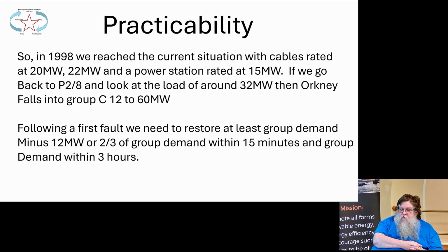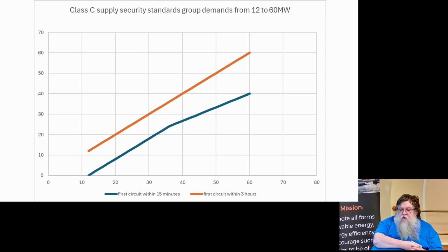If we go back to P2/8 and look at the load of around 32 megawatts, then Orkney falls into Group C, 12 to 60 megawatts. And following the first fault, we need to restore at least group demand minus 12 megawatts, or 2/3 of the group demand within 15 minutes, and group demand within 3 hours. There's a graph showing that. You could use this graph to see where 32 megawatts is, and see 32 megawatts is about there. You've got to get 20 back within 15 minutes, and the whole 32 within 3 hours.